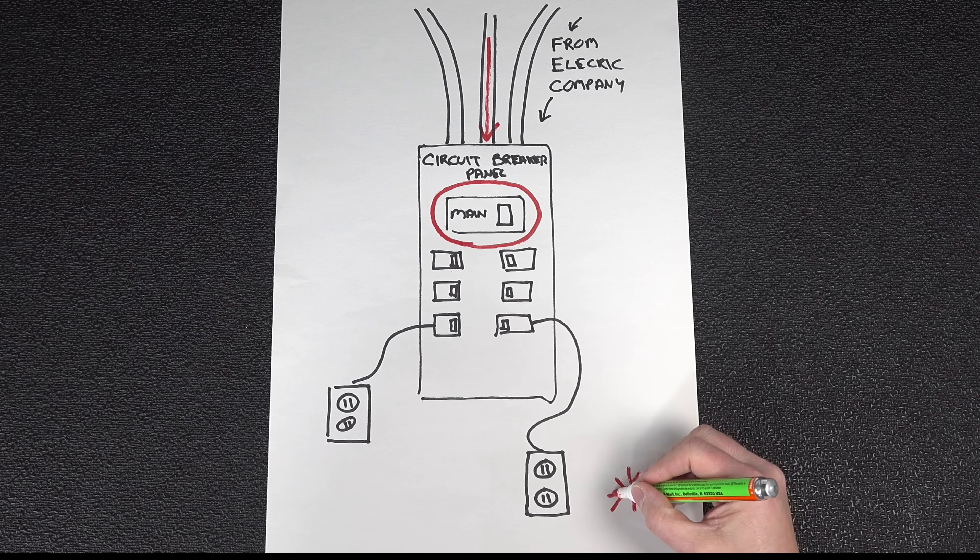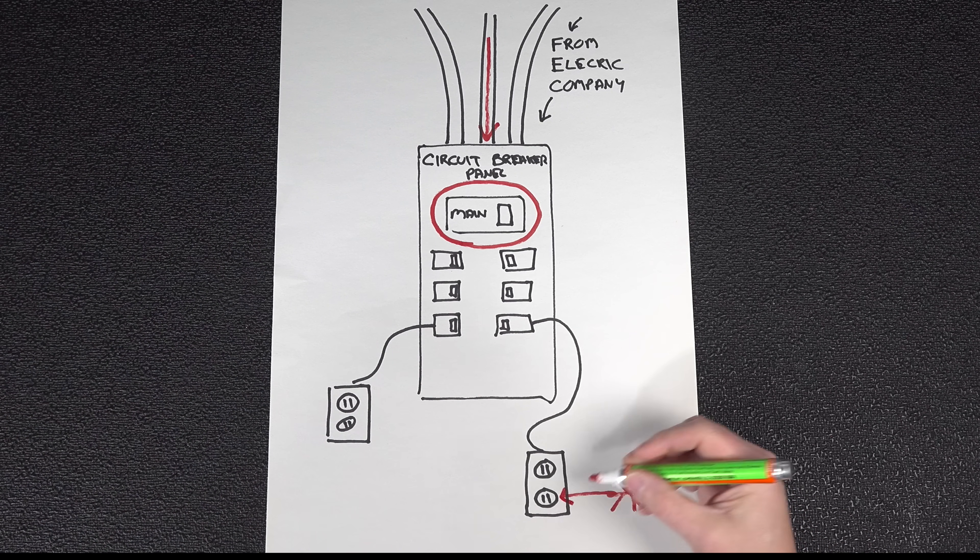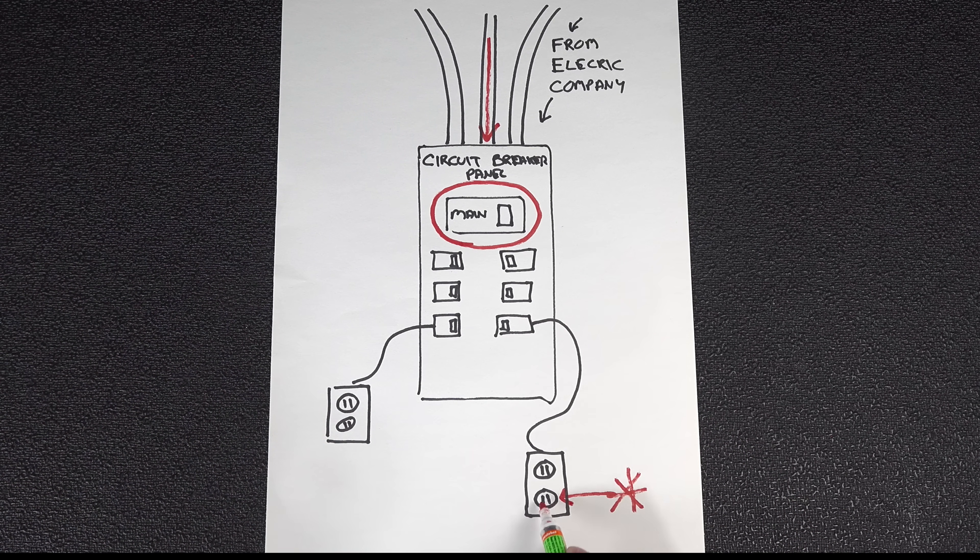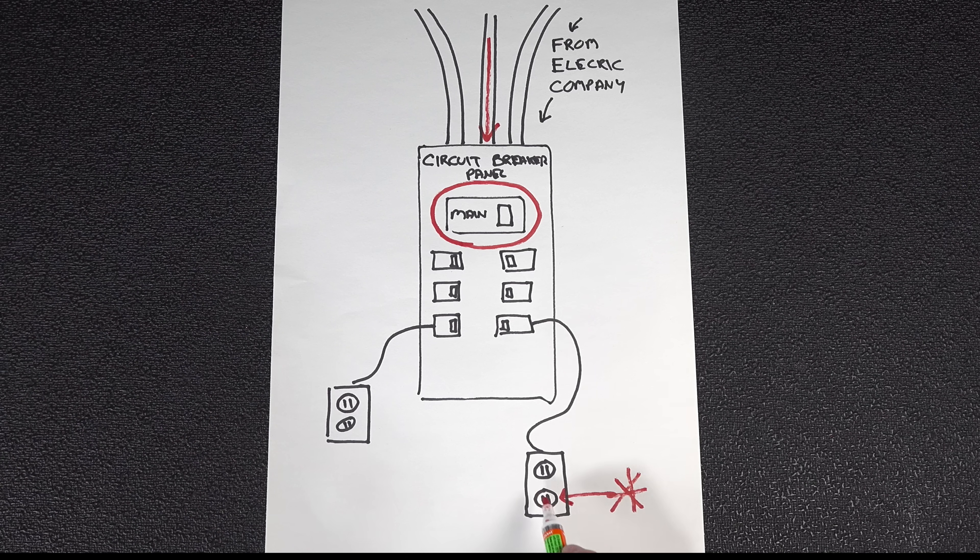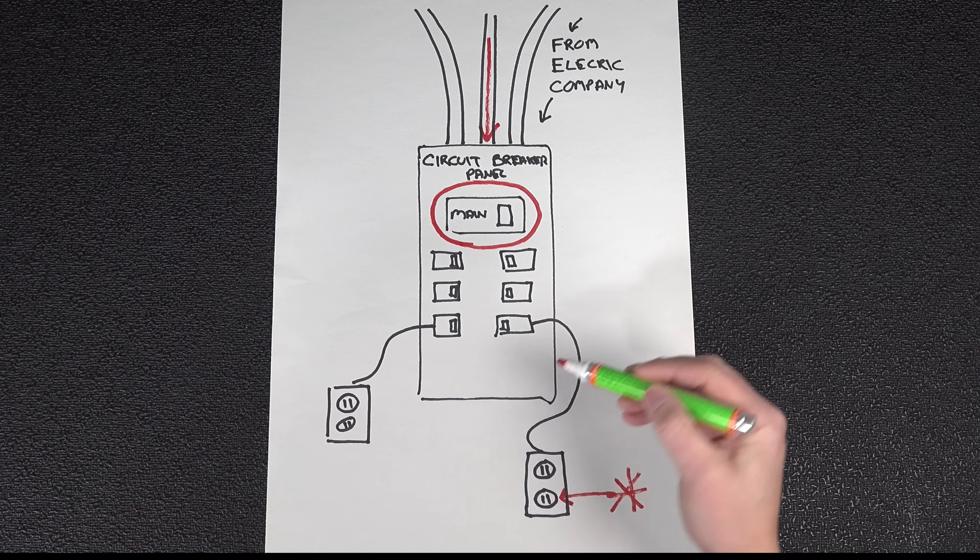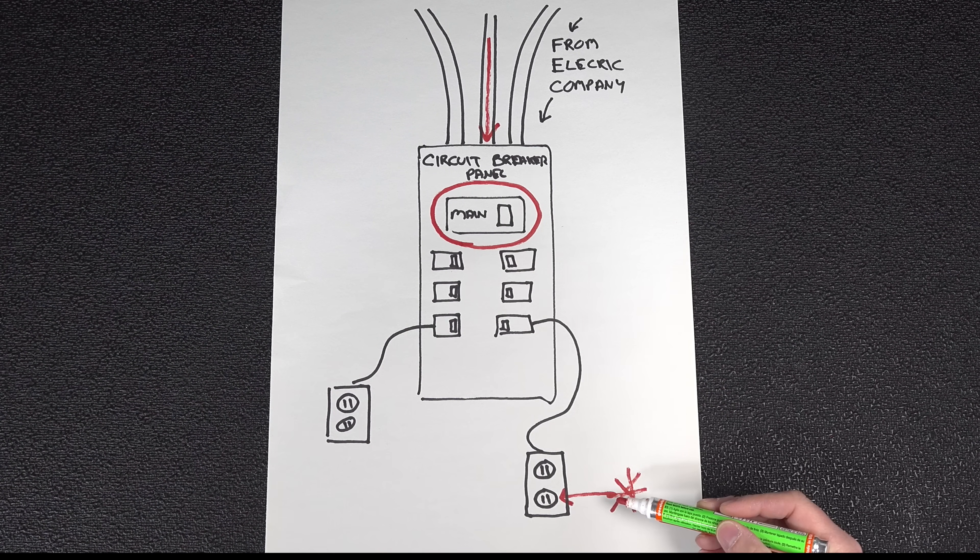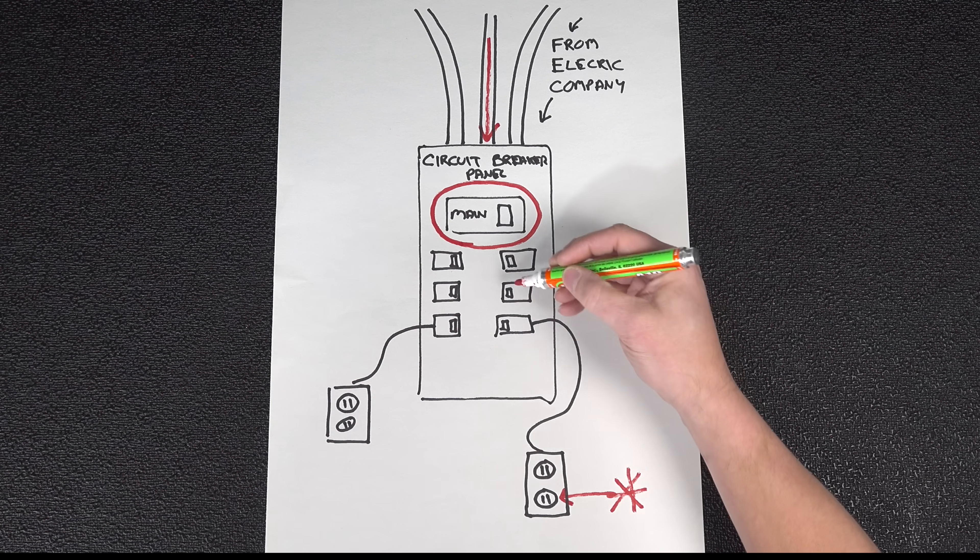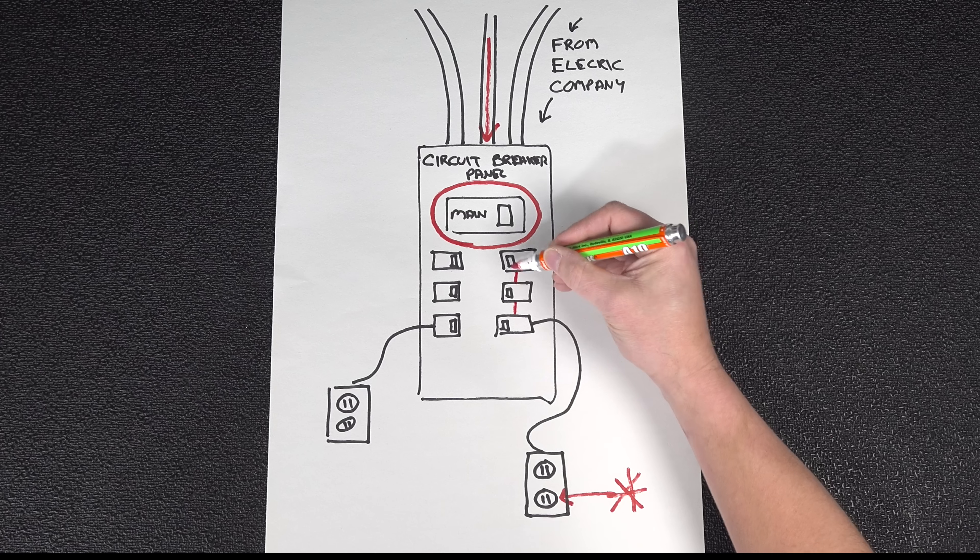Now you might think backfeeding sounds great, but it's completely illegal and totally unsafe. The reason it's illegal is because electricity doesn't just stop at your circuit breaker panel. If you backfeed your system through one of your outlets, it would keep flowing all the way back up to the street. Even your neighbor might be able to use some of the power from your generator.